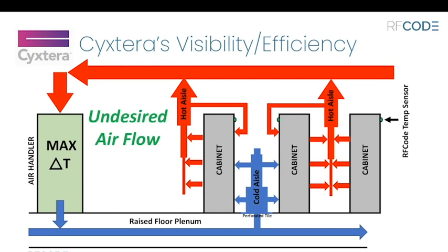So when we started doing this, our concern was that our floor techs would be running around like crazy, making adjustments continuously, and we just found that wasn't the case at all. The floor temperature variations simply weren't nearly as dynamic as we feared they might be, and these location-specific adjustments were maybe just a few a day. And then the teams learn through experience over time how their sensors react, and of course they adjust their response accordingly. All right, so that's the efficiency by managing the cold aisle in this case, and essentially virtual containment, because we actually don't have any hard containment there whatsoever.